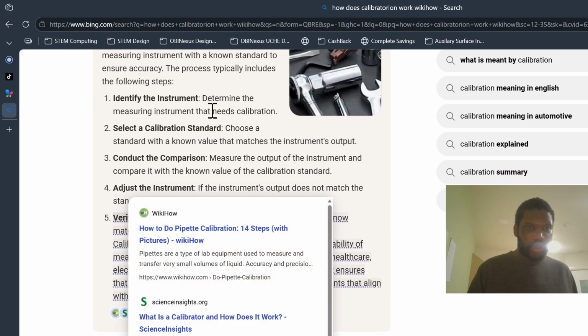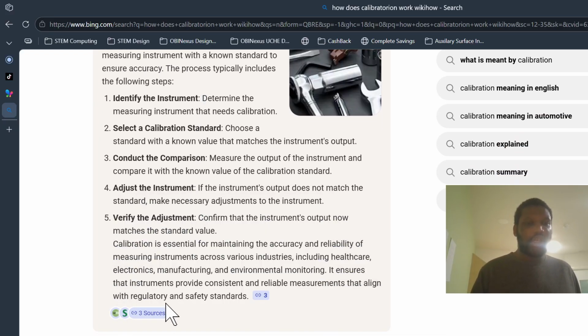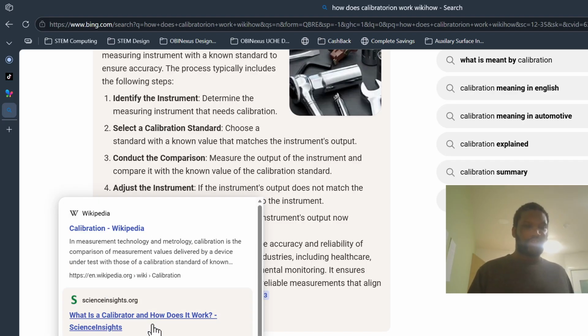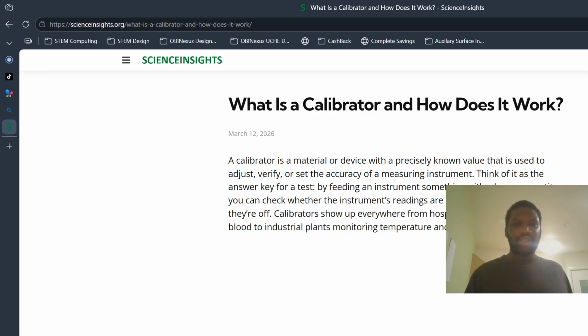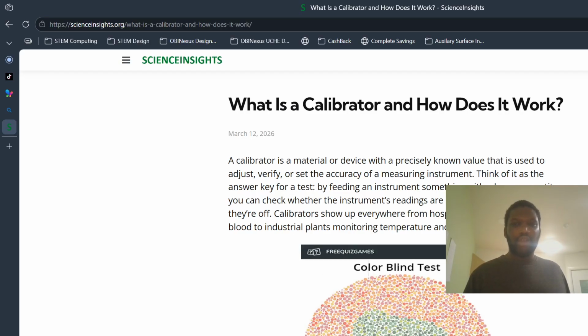Oh, it's gone. Identify an instrument, determine the... oh yeah, tuning the guitar is calibration. What's a calibrator? A calibrator is a material device that precisely knows values that is used to adjust, verify, or set the accuracy of measuring instruments. Think of them as...